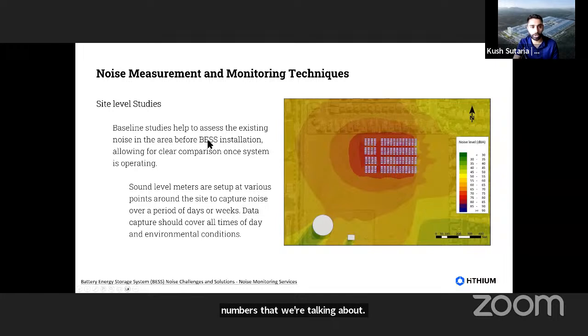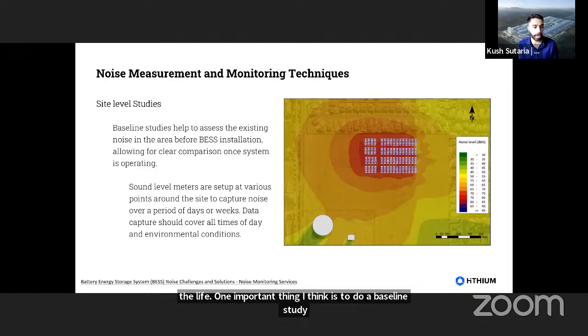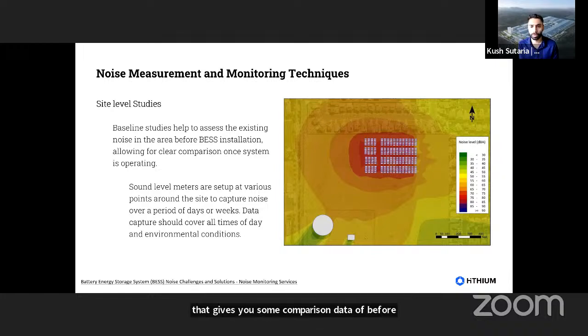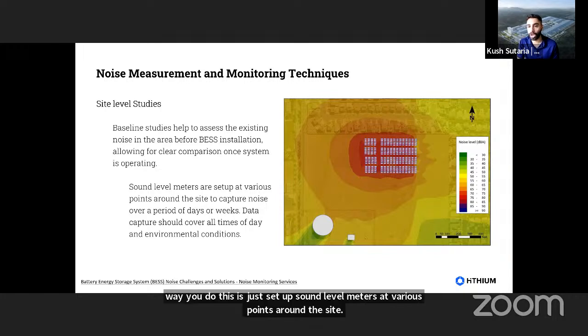Before we get on to mitigation strategies, what are some techniques we can use to measure sound and monitor it throughout the life? One important thing is to do a baseline study of the ambient noise at the site before you've installed any BESS. That gives you comparison data of before and after that you can use to assess the effectiveness of your noise reduction systems. It can also be a tool to use with local communities, to show that noise has been less than predicted, or is right around the ambient noise it was before installing the BESS. So it's important to do this, and generally the way you do it is set up sound level meters at various points and distances around the site, covering the full time period, day and night.